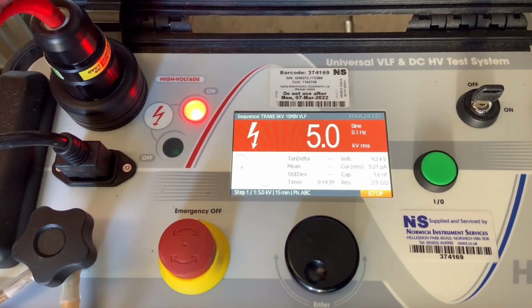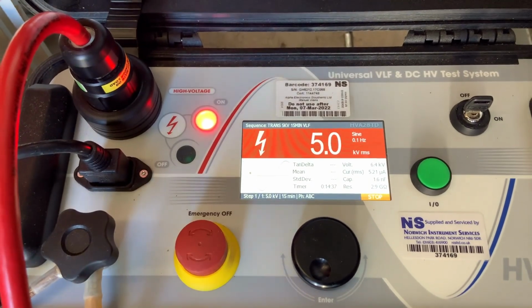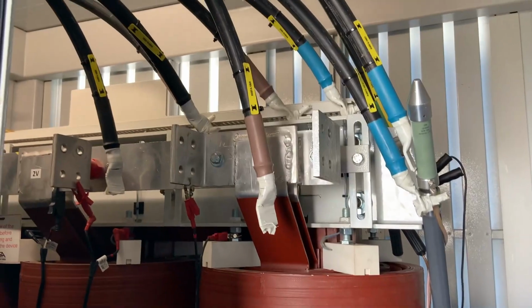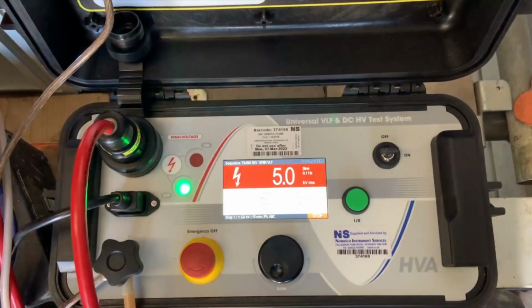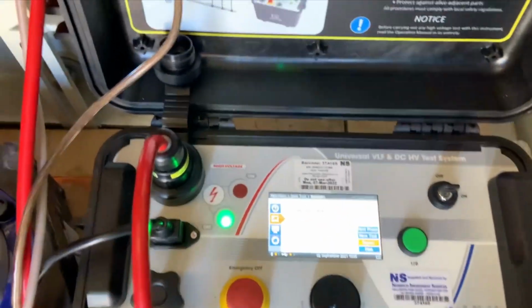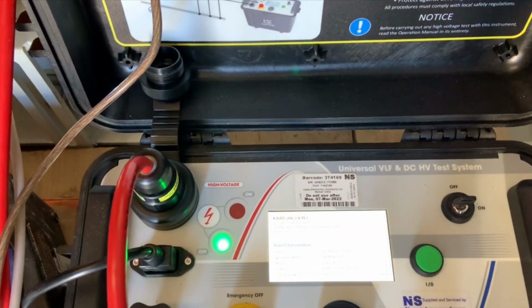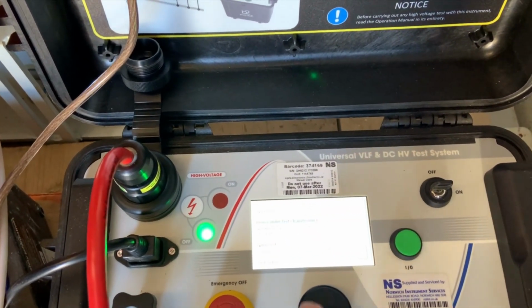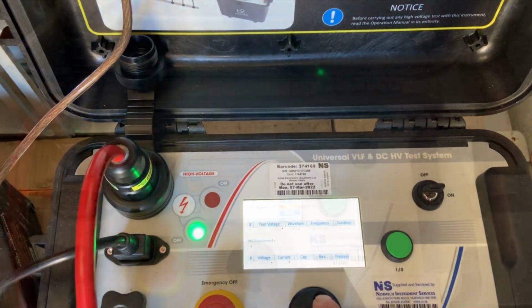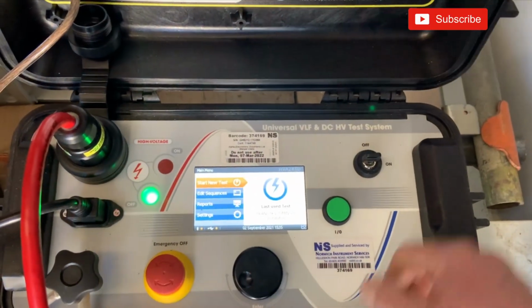transformer hasn't degraded. There's many tests you can do on a transformer. This is just 3 examples of the tests that can be performed for insulation resistance of the windings. If you ever find yourself investigating a transformer that has tripped on the HV side due to overcurrent or earth fault, these tests are a good place to start.